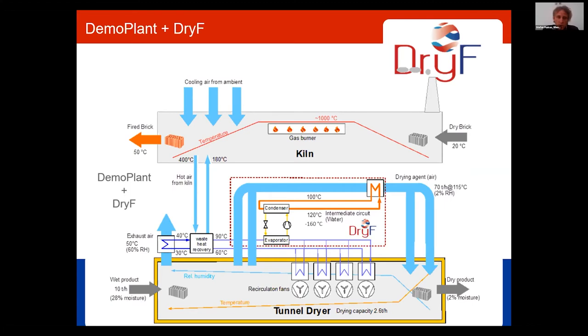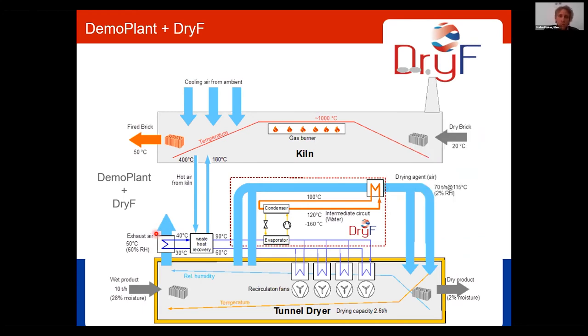and is providing cold water that is sprayed into the cooling tower and the scrubber, where the moist air from the dryer goes through, and we gain warm water of about 40 degrees Celsius. The absorption heat pump lifts this temperature to 90 degrees, and with this water, we go into the dryer. You do not see my pointer, do you? Laser pointer here. So we have here the wet air scrubber. We have an absorption heat pump driven by excess heat from the kiln. It provides 90 degrees water, and internal heat exchangers in the dryer are used to operate the dryer.